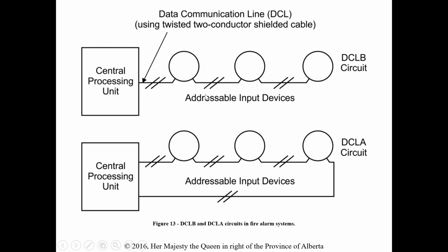Again, a little bit more wiring on that, but this is, I would say, a smart system compared to a conventional system. Especially a conventional B system that has end-of-line resistors would probably be the most basic system. This is definitely more of the Cadillac, if you will, and a lot easier to maintain and troubleshoot and, I guess, make sure it's operational because it's constantly checking all the time.